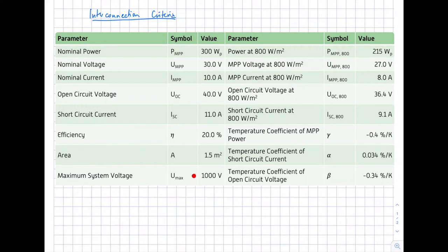What we also need to know is the maximum system voltage of the modules — this is typically 1000 volts. If the voltage of your module string exceeds this upper limit, you might damage your module. Typically this value is not that critical, as inverters have a similar maximum system voltage level, but keep it in mind so you don't exceed this limit.